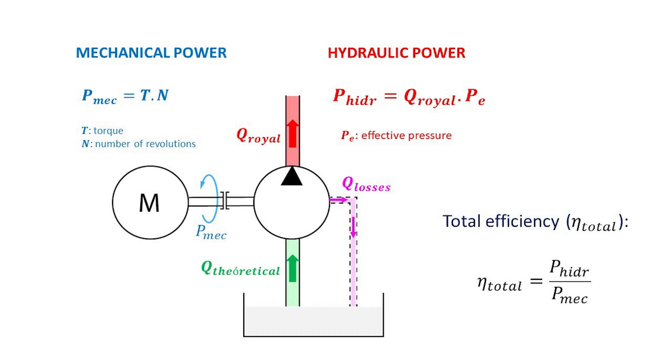The mechanical power can be obtained by multiplying the torque generated by the engine by the number of revolutions. And the hydraulic power is equal to the effective volumetric flow, or real flow, multiplied by the effective or relative pressure at the pump outlet. So from there we have another relation to obtain the total efficiency of the pump.